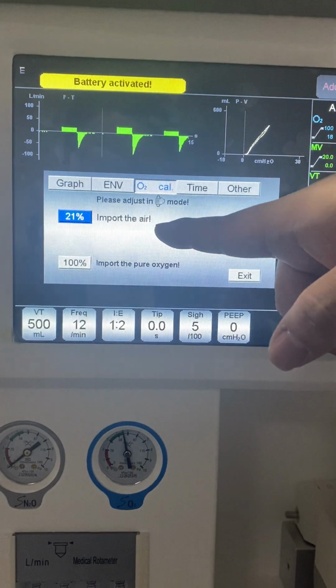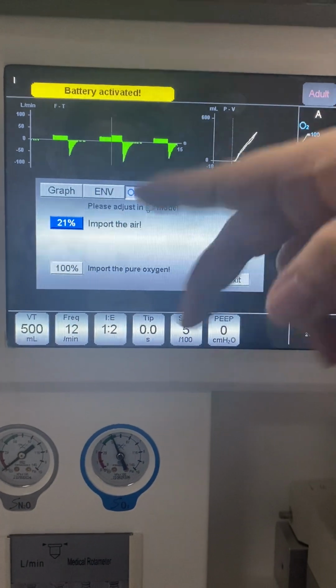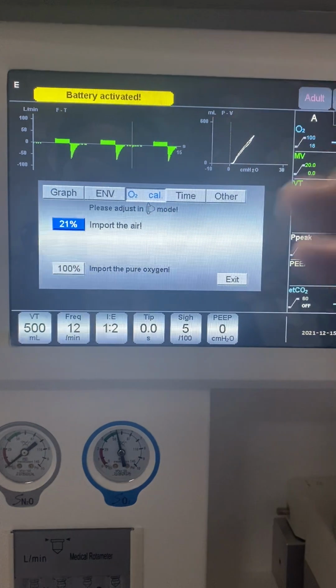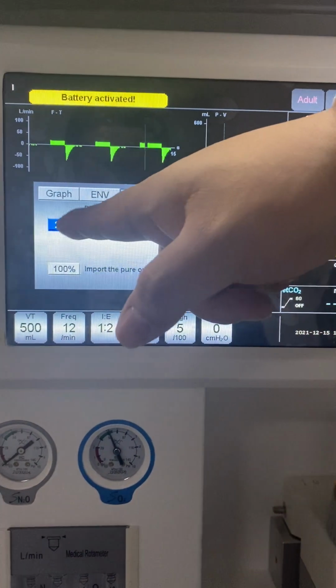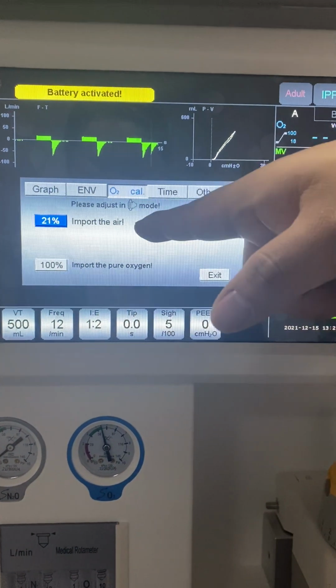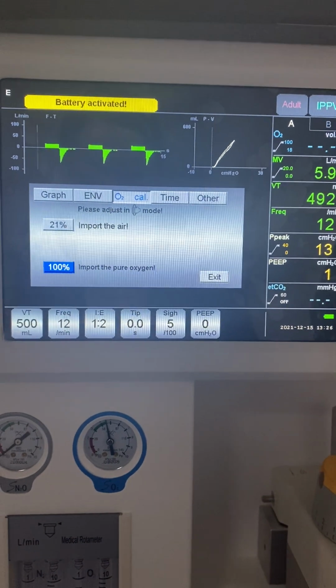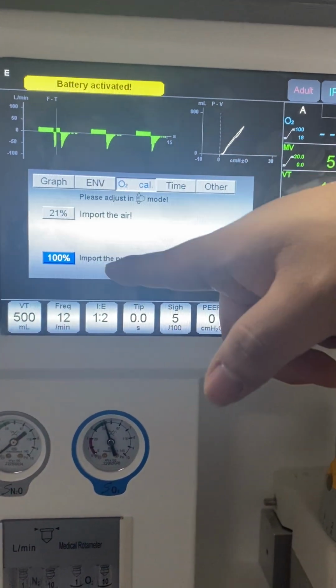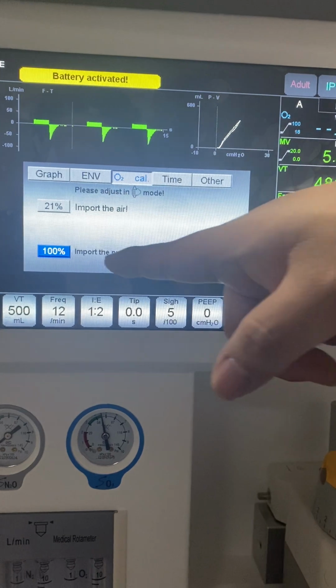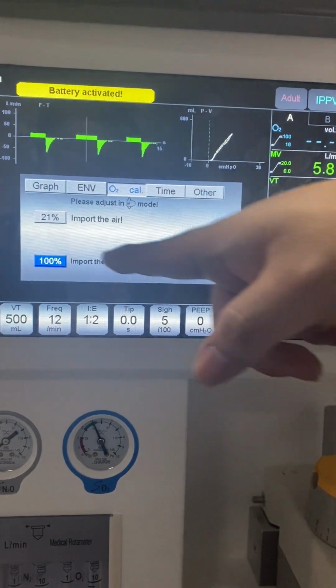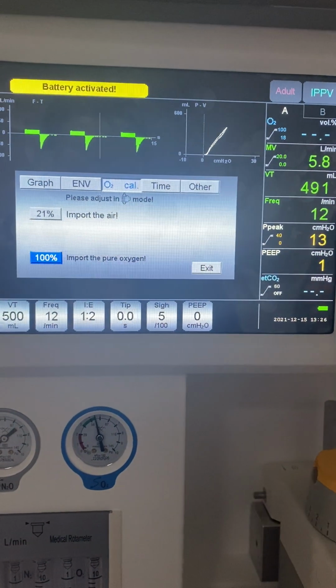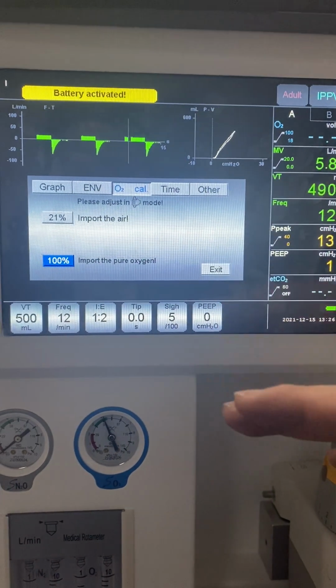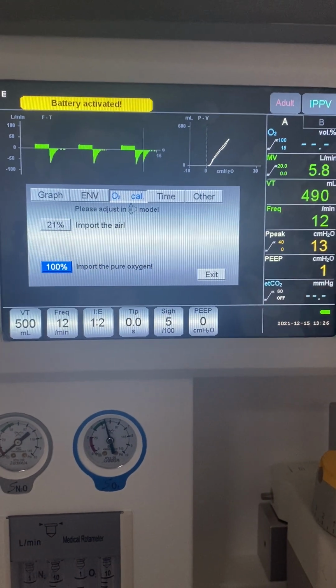So for the 21%, we only input the air. That means you only connect the air pipeline, and do not connect the oxygen pipeline. And then we press here. After 10 seconds, it will show complete. And then we change to 100%. You take out the air pipeline and only connect the oxygen pipeline. Then we press it. Also after 10 seconds, it will show complete. So then the oxygen calibration is finished. It's very easy to operate.